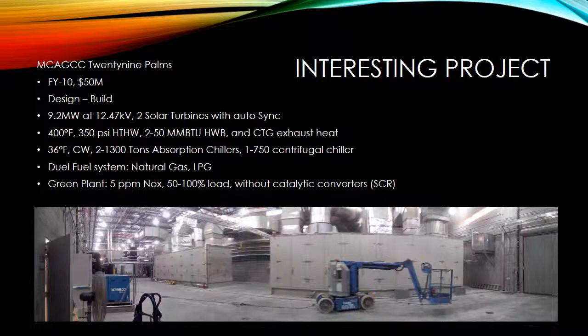The plant uses natural gas as a fuel source to feed two 4.6 megawatt combustion turbines by Solar Turbines. And we use the heat from the turbines exhaust to feed two 1,300 ton absorption chillers to produce chilled water for cooling, and also feed two heat recovery boilers to produce high temperature hot water for heating. As a supplement to the heat recovery boilers, we also have installed two 50 million BTU hot water boilers for high temperature hot water production. The plant uses natural gas as the main fuel source, and the backup fuel is LPG. And we also installed on-site storage for the LPG, on the order of 250,000 gallons.